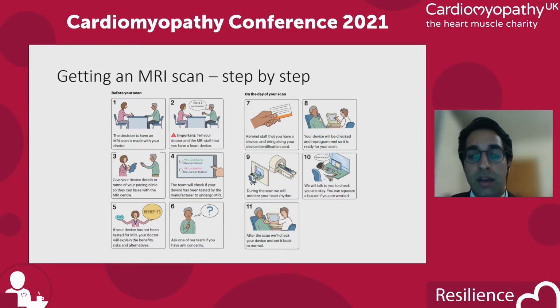So this is the modern process of getting an MRI scan if you have a pacemaker or defibrillator. I'll just walk you through this. So before the scan, looking at number one, a decision should be made first with your doctor, and that's the referring person for the MRI scan. They, of course, need to be aware that a device is present, and you need the technical details of the device, which need to be passed on to the MRI scan. And the reason for that is to check exactly what that device is. And I'll go into that in more detail because that will determine how the scan is performed safely. Some devices may not have been tested in an MRI environment, and these need a separate pathway where we need to consider other options as well and the potential small risks of these.